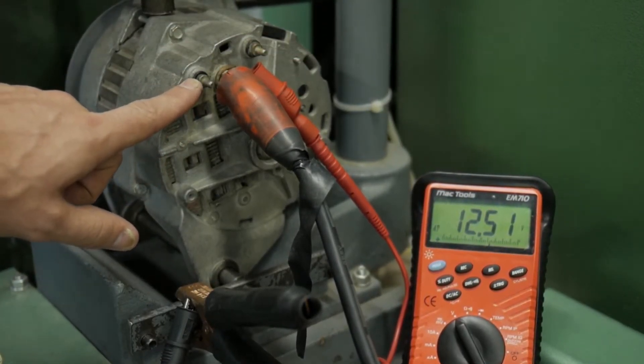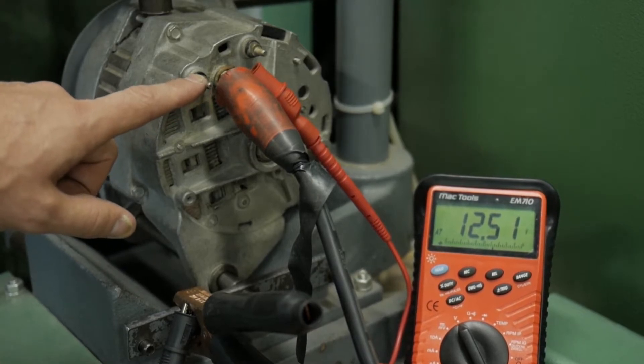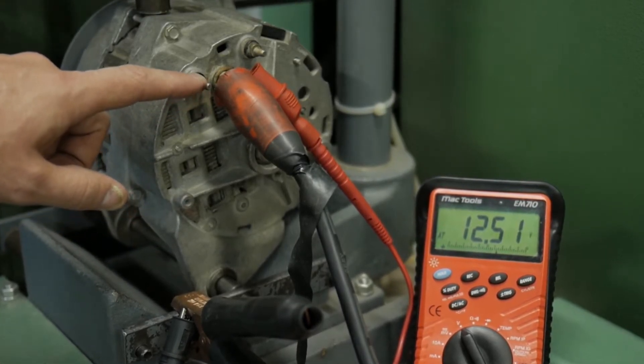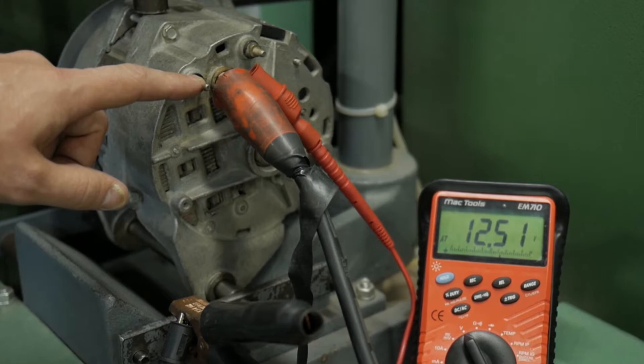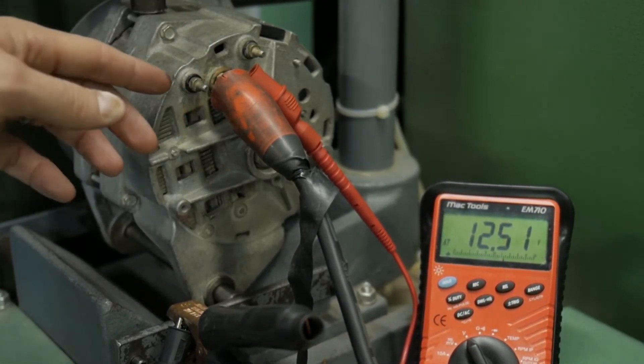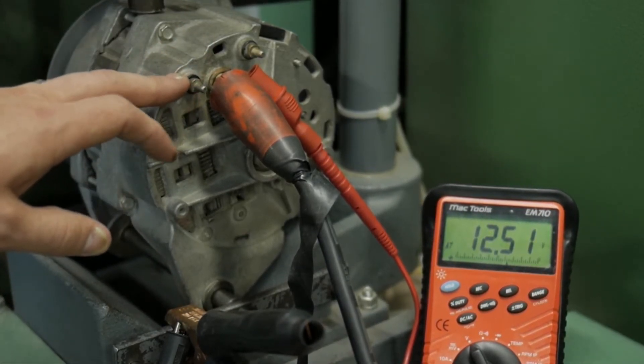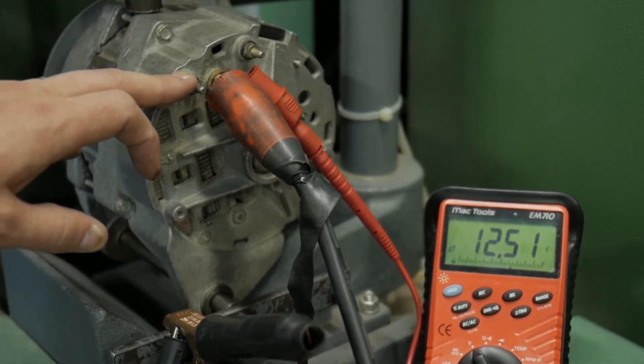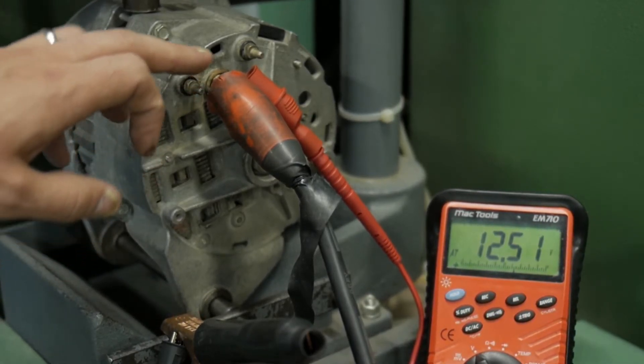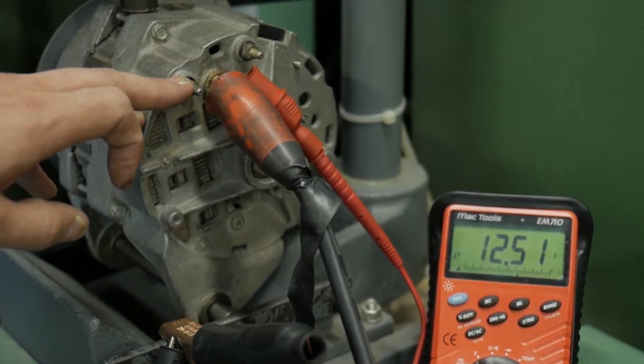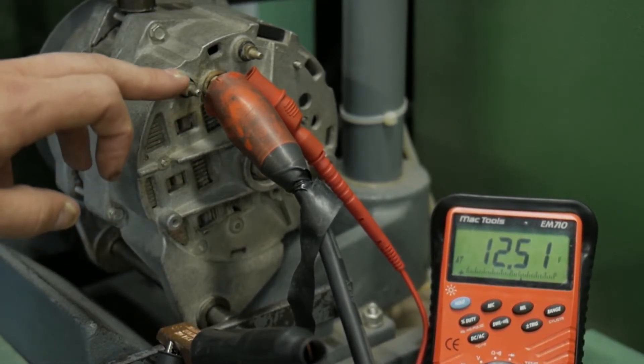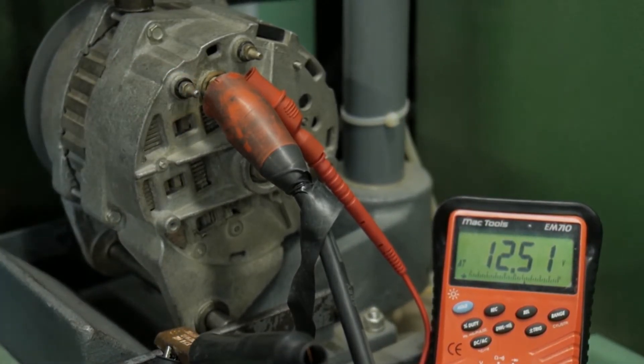That's the residual terminal to excite the rotor field, which will produce an output from the alternator. What's happened is the residual magnetism of the rotor has dissipated. We're going to reintroduce it, essentially bypassing the regulator and directly full-fielding this alternator.